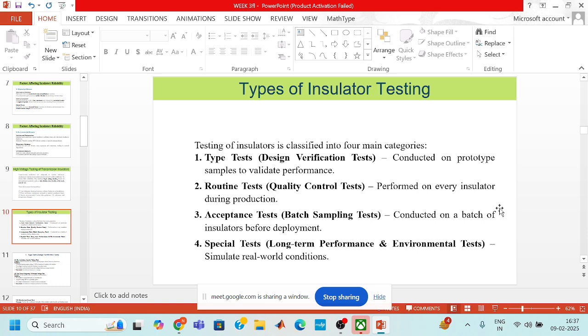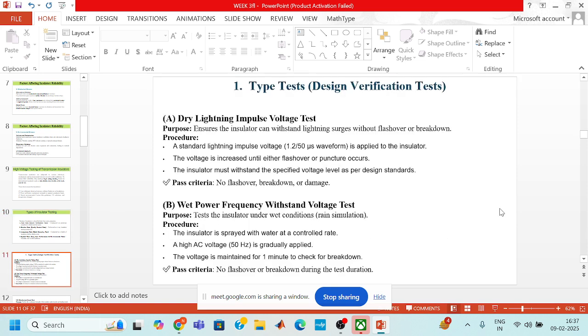Now, the fourth one is the special test, also known as the long-term performance and environmental test. It is used to simulate real-world conditions. Now, the first test is the type test. Under this, there are some different categories. First is the dry lightning impulse voltage test. By doing this test, it ensures that the insulators can withstand lightning surges without flashover or breakdown.